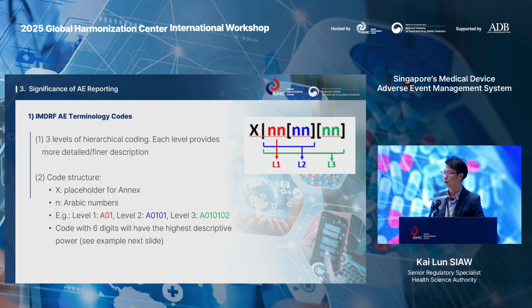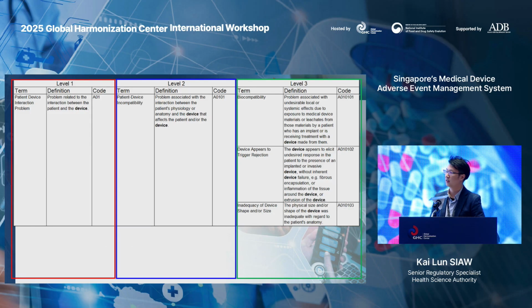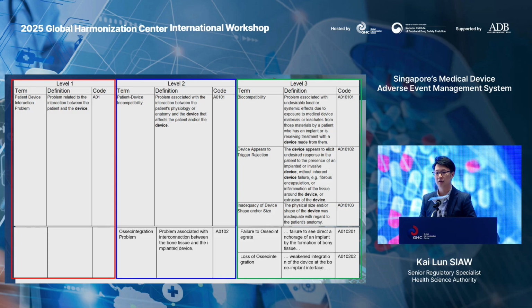So this is how the IMDRF code looks like. There are 3 levels, and the lower you go, at L3, the more details of the event it contains. To put it into perspective, here's an example of an A01 code. It just says patient device interaction problem. But if you go down to level 2, you can see that it's either a patient device incompatibility or an issue with integration with the bone. Then if you go down to level 3, you can break it up into more information, such as whether the device triggers a reaction, or inadequacy of device shape and size. We normally try to use the lowest level because it gives us more information about the event. The beauty of this is that during trend analysis, you can do a simple filter and it can give you the data analysis outputs that you desire.